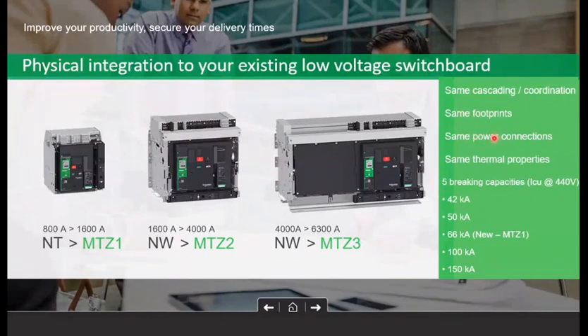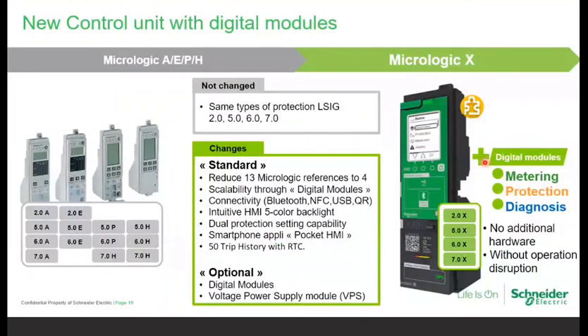We have a same power connection, so it means the vertical and horizontal terminals at the site are replaceable, are available with the MTZ also. We have same thermal properties also in MTZ in addition to the NW. So our thermal properties, footprint and the mechanical sizing dimensions are same for the MTZ, but we have got a new trip unit, new control unit in the MTZ.